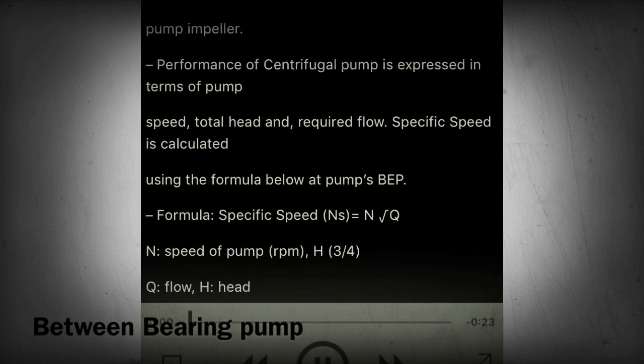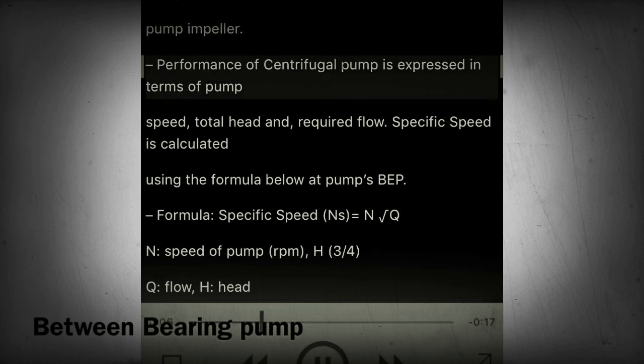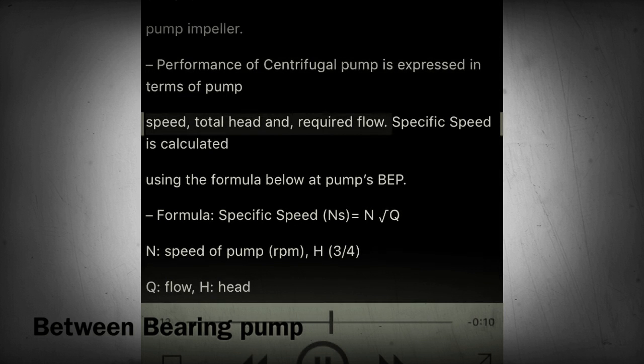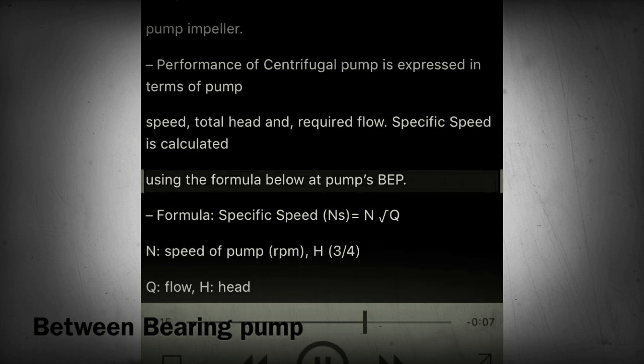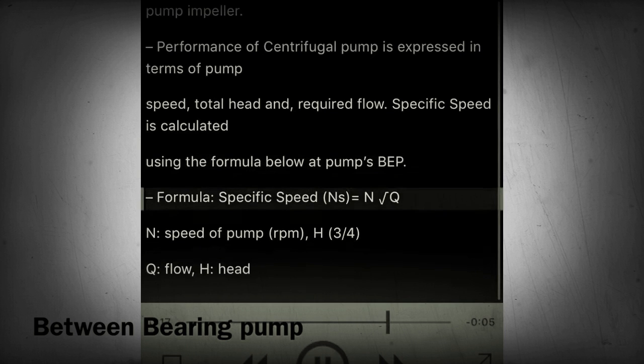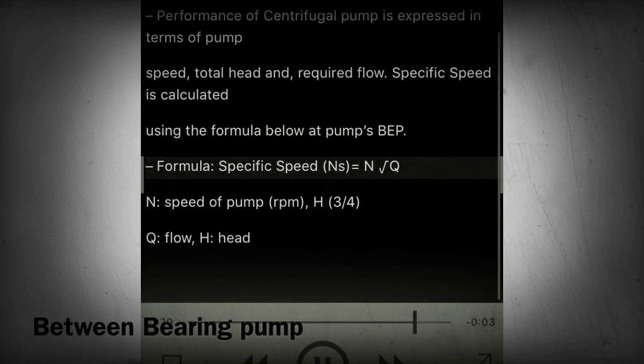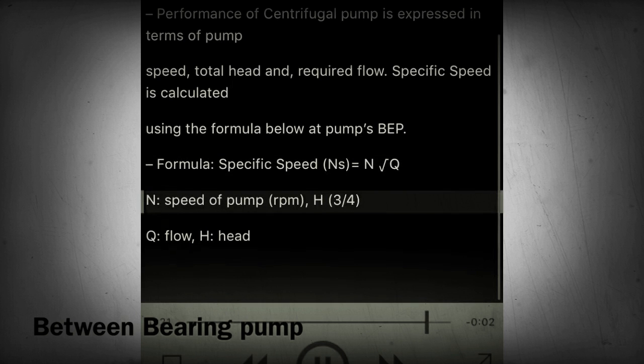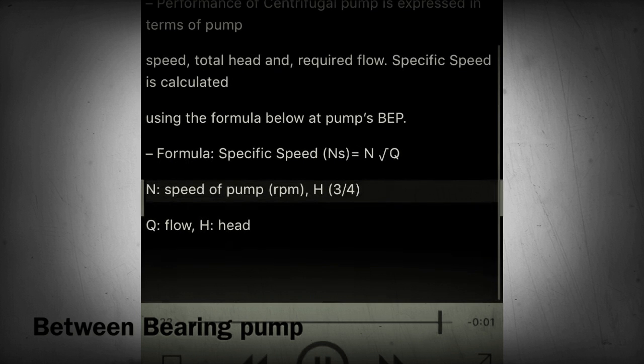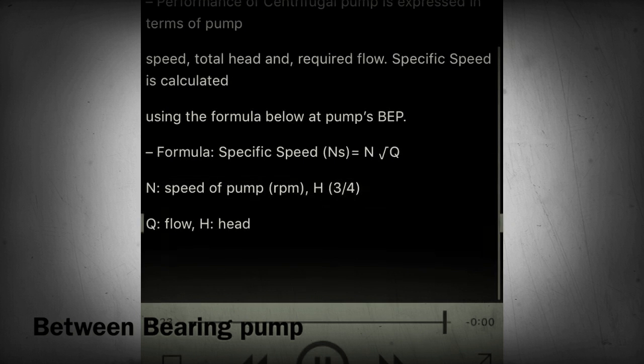Section 28 - Specific speed. Specific speed is used to describe the geometry and shape of a pump impeller. Performance of a centrifugal pump is expressed in terms of pump speed, total head, and required flow. Specific speed is calculated using the formula at the pump's BEP: Ns = N × √Q / H^(3/4), where N is speed of pump in RPM, Q is flow, and H is head.